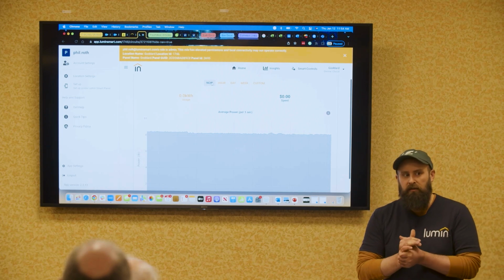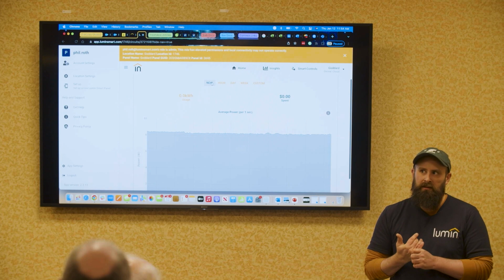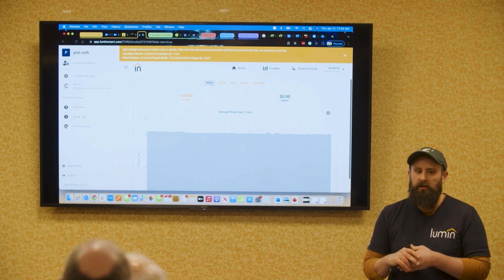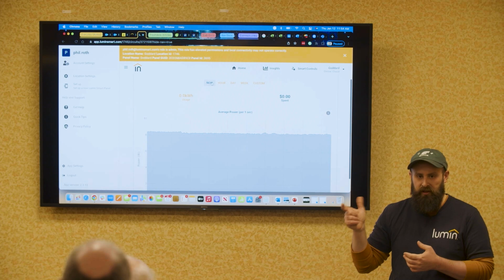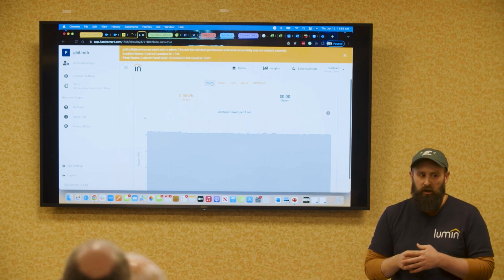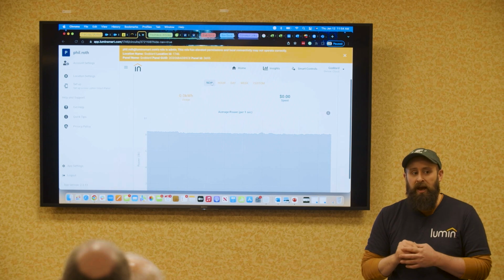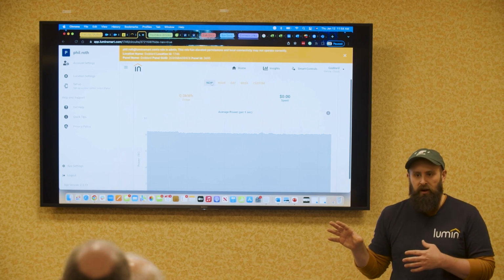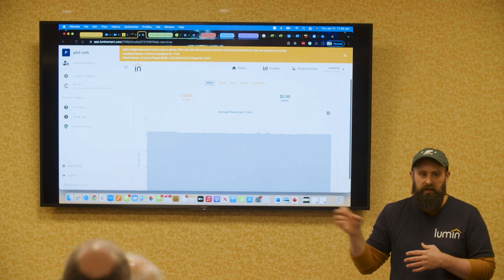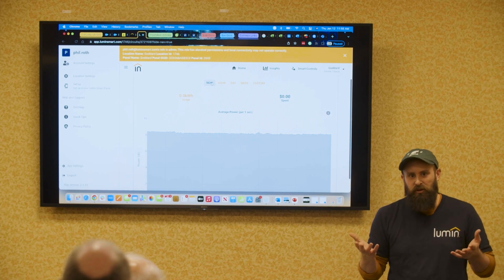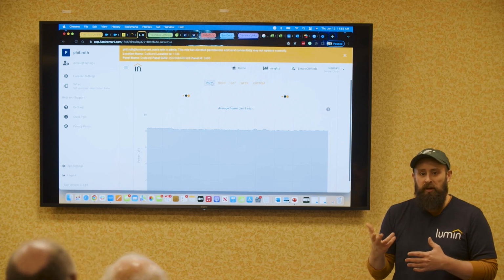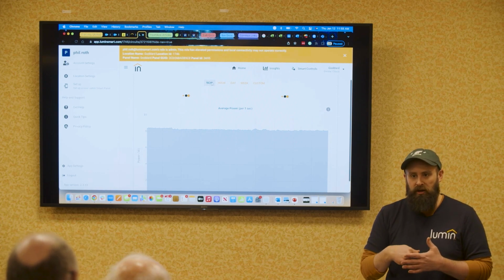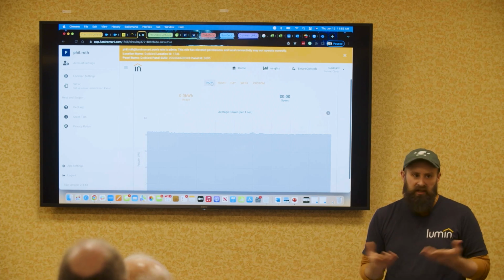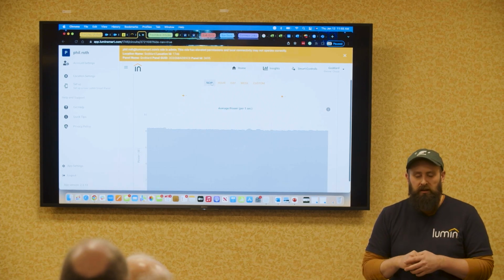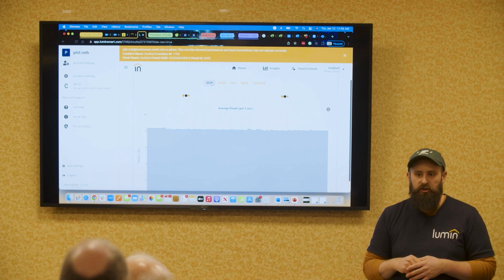Now there are a few transfer switches - well actually no, most transfer switches are fine, but there are a few microgrid interconnect devices that transfer a bit slower. We've had a few ride-through issues where the transfer has been slow enough that the Lumin has lost power, and then of course no load shedding happens at all. For that, we do have a plug-in temporary power unit, just a capacitor, as an extra purchase. So if need be, there's a port for it, and now you have about 100 seconds worth of power, which should get you through any ride-through issues.